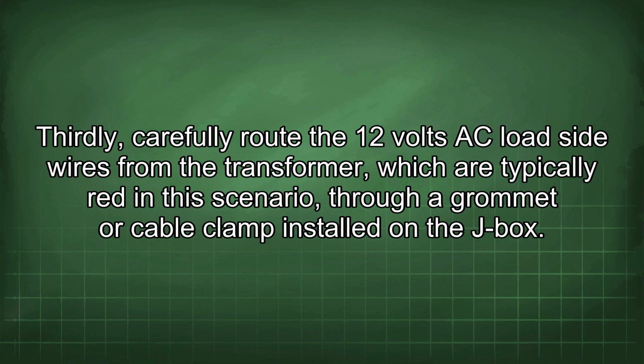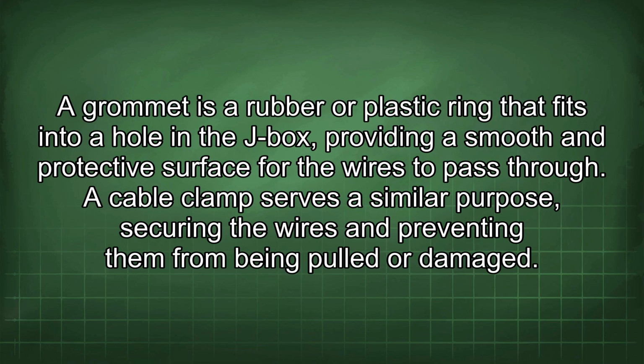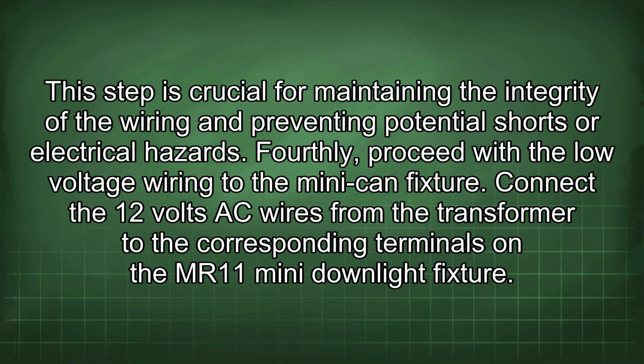Thirdly, carefully route the 12 volt AC load side wires from the transformer, which are typically red in this scenario, through a grommet or cable clamp installed in the J-box. A grommet is a rubber or plastic ring that fits into a hole in the J-box, providing a smooth and protective surface for the wires to pass through. A cable clamp serves a similar purpose, securing the wires and preventing them from being pulled or damaged. This step is crucial for maintaining the integrity of the wiring and preventing potential shorts or electrical hazards.